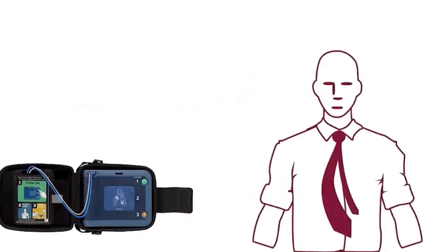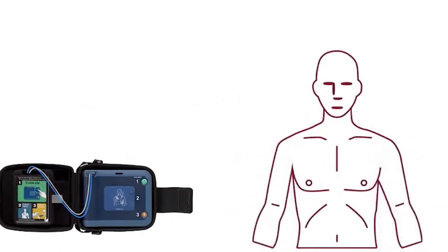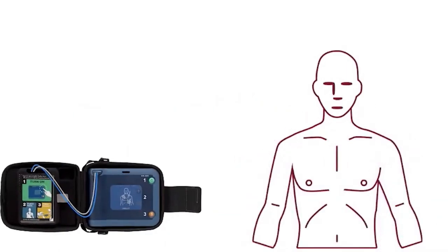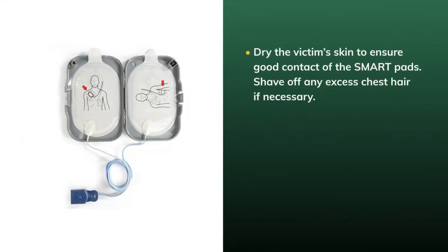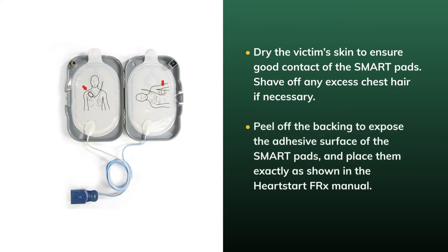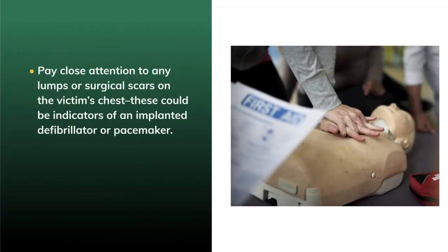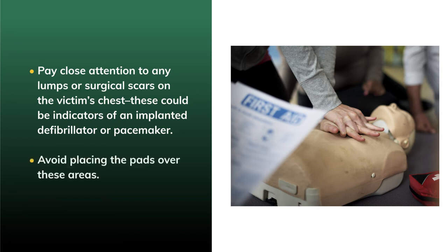The device will direct you to remove all of the clothing from the victim's upper body. Then, remove the smart pads case from the unit's carrying case. Dry the victim's skin to ensure good contact of the smart pads. Shave off any excess chest hair if necessary. Peel off the backing to expose the adhesive surface of the smart pads, and then place them exactly as shown in the HeartStart FRx manual. Pay close attention to any lumps or surgical scars on the victim's chest. These could be indicators of an implanted defibrillator or pacemaker. Avoid placing the pads over these areas.